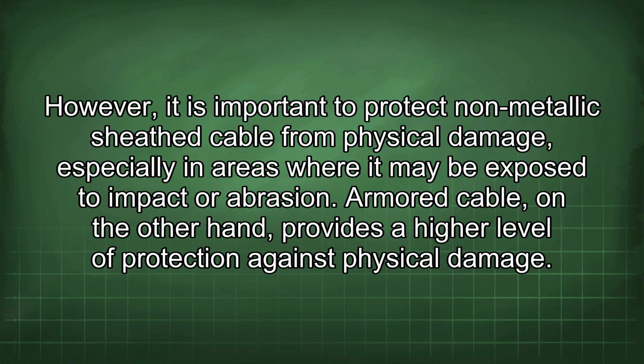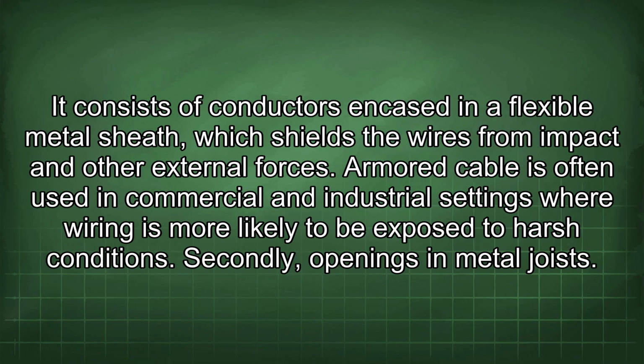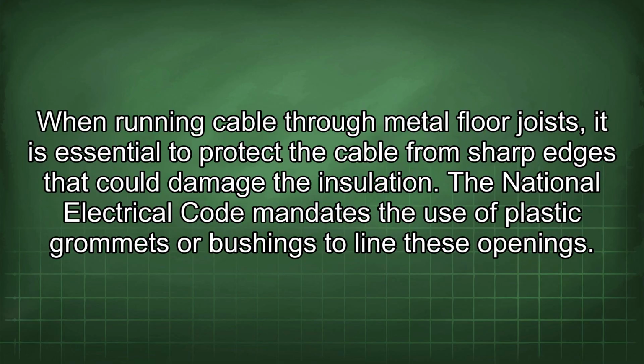Armored cable, on the other hand, provides a higher level of protection against physical damage. It consists of conductors encased in a flexible metal sheath, which shields the wires from impact and other external forces. Armored cable is often used in commercial and industrial settings where wiring is more likely to be exposed to harsh conditions. Secondly, openings in metal joists. When running cable through metal floor joists, it is essential to protect the cable from sharp edges that could damage the insulation.